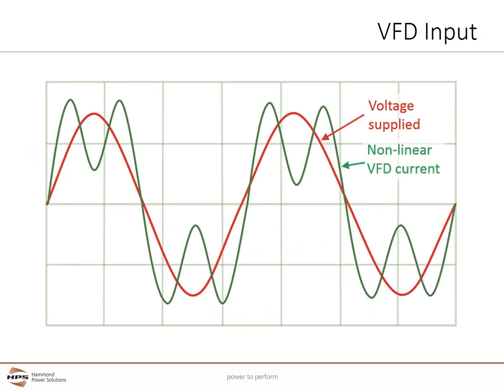The input or line side of a VFD uses rectifiers and is basically a DC power supply. This creates current harmonics when it transforms AC to DC power. As a result, the harmonics distort the utility's perfect red sine wave to make it look like the green wave. The VFD's input section also has sensors to monitor the incoming power and resultant DC bus voltage. Current harmonics can cause significant issues within a facility, and if they exceed a standard called IEEE 519, the utility can fine the user.